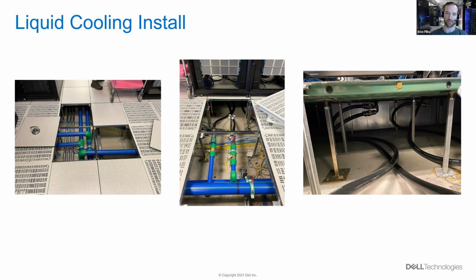When you want to connect a rack, you put the manifolds we saw in the previous picture underneath the floor, and you connect it with quick disconnects. This system is very flexible because it doesn't require you to have all the racks ready to go on day one, and we didn't. We have 10 racks of capacity.